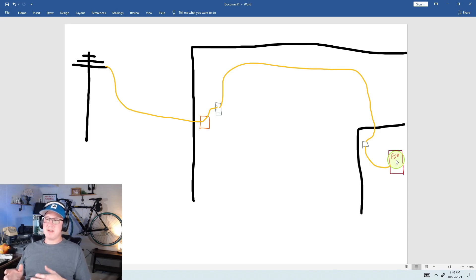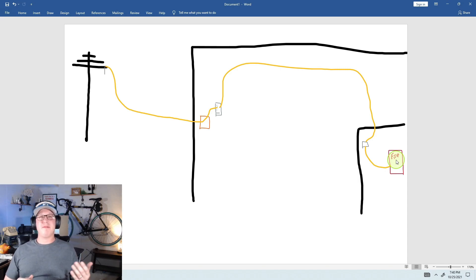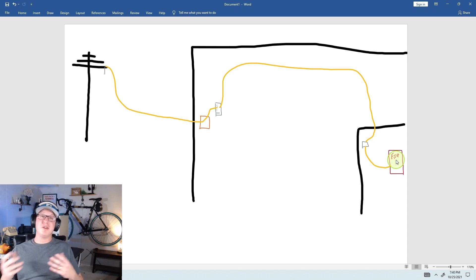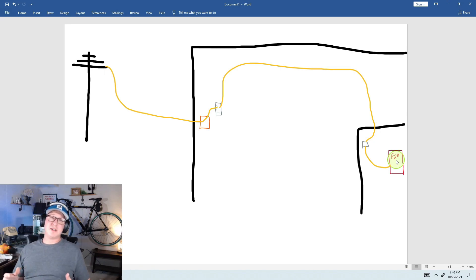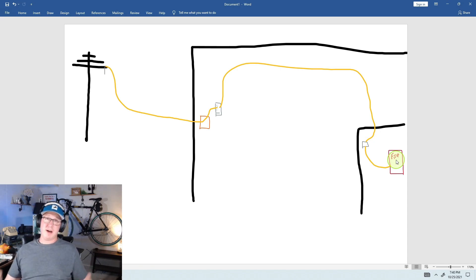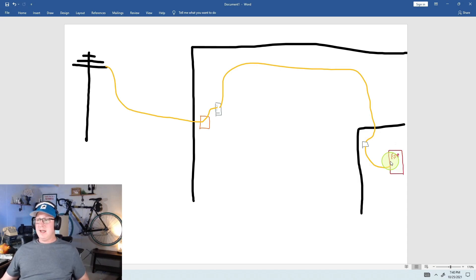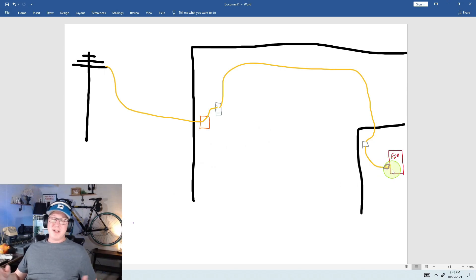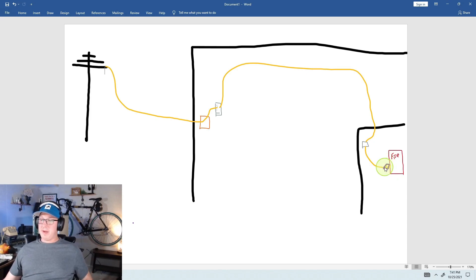So the reason I bring this up is I've had to troubleshoot a lot of these, because sometimes these lines will go bad, or the panels will go bad. What will happen is the fire company will call in, and it won't get a response. So they will contact the company, which the company usually contacts you, and they say that the fire panel isn't responding, and we need to figure out what's going on. What we would do first is we go to the fire panel. We'd have to find it wherever it is in the maintenance closet. Sometimes you have to open these up. You would disconnect it directly from the fire panel, and then you would hook up your butt sets. Or for me, it's my old telephone that I bought from Walmart.